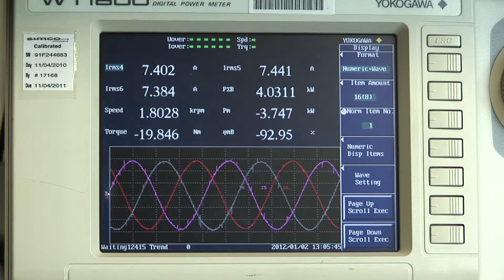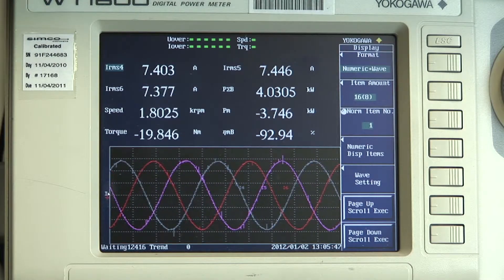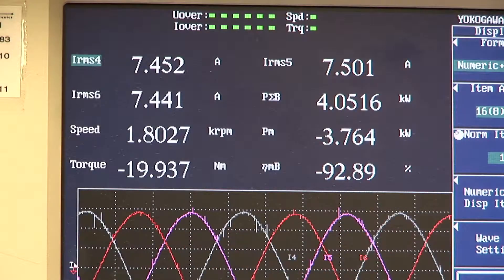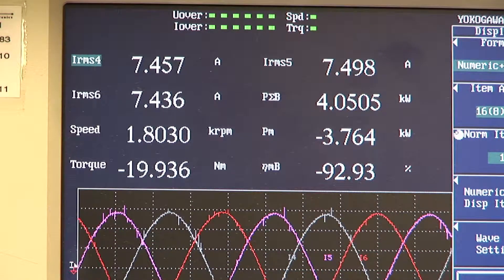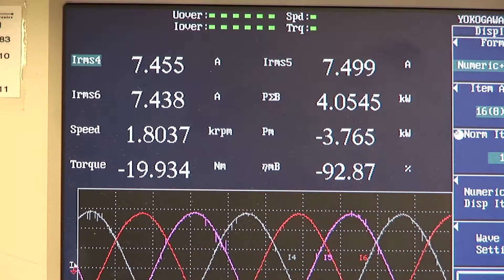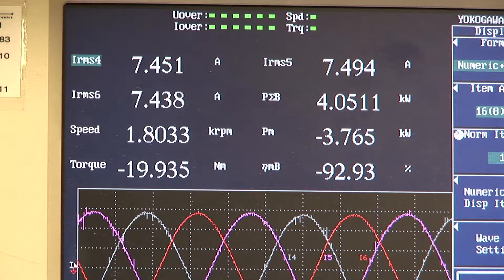At the motor's rated 5 horsepower operating point at a speed of 1800 rpm and 20 Newton meters of torque, we see that the premium plus motor's efficiency is almost 93 percent.